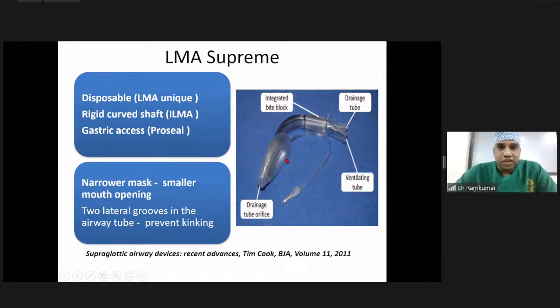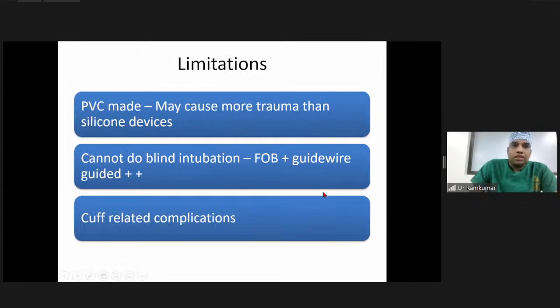The advantage is that it has a narrow mask, so it is easy to insert with a smaller mouth opening. Normally a two-finger, two-centimeter mouth opening is required to insert a laryngeal mask airway. This has a little advantage in placing it. It also has two lateral grooves on either side of the tube, which prevent airway tube kinking as well. The limitations are here. It is made of PVC, so there's more chance of trauma compared to silicone devices. And the problem is the drain tube runs in the middle of the ventilation airway lumen, so it's difficult to do a blind intubation.